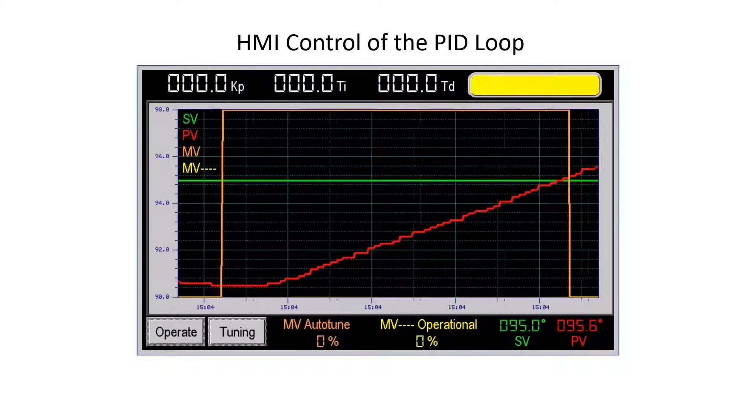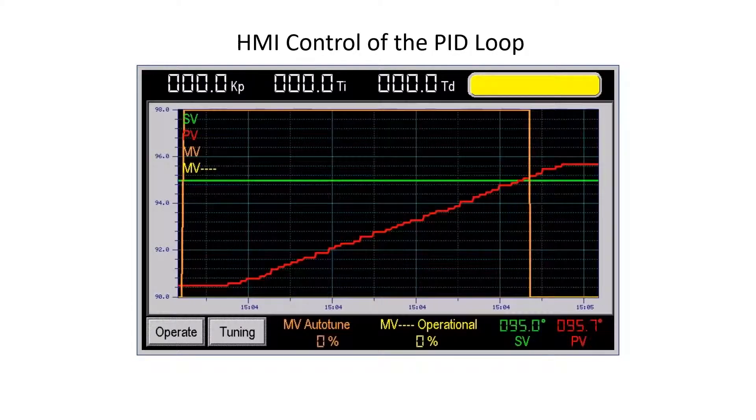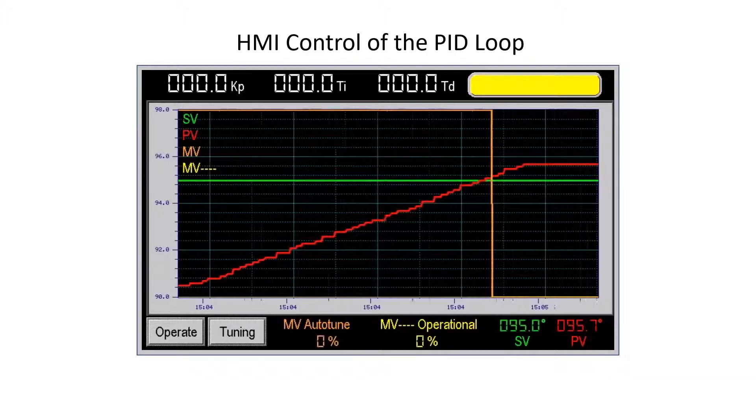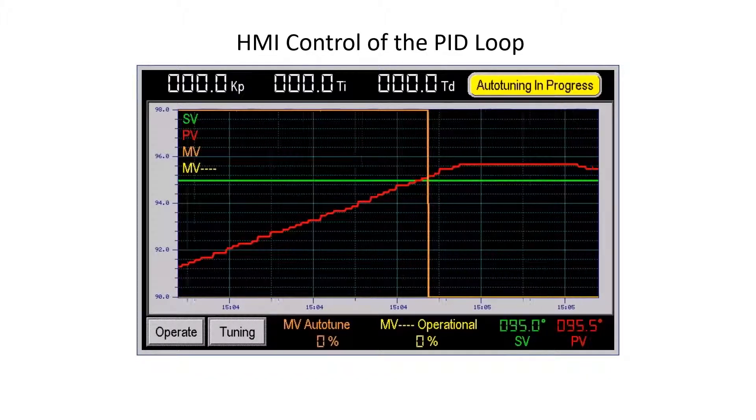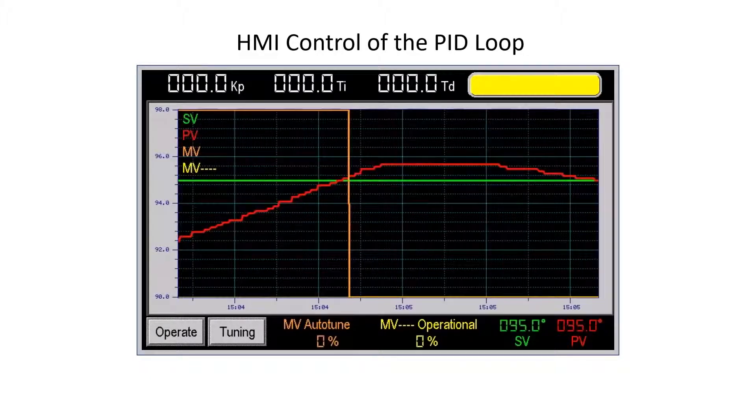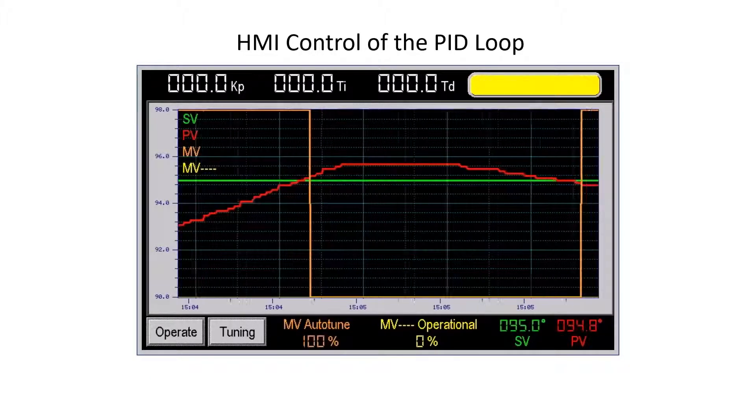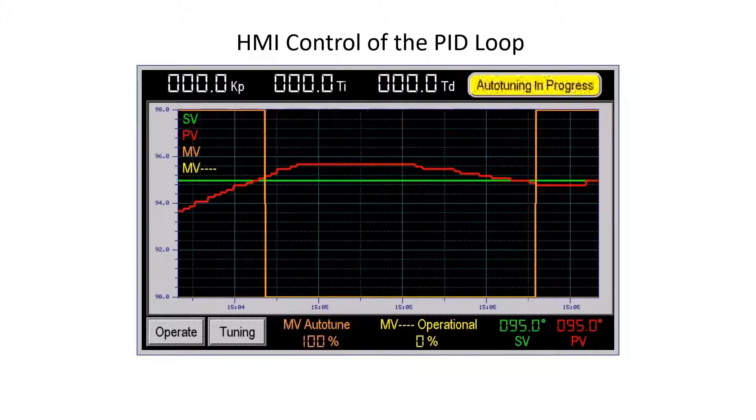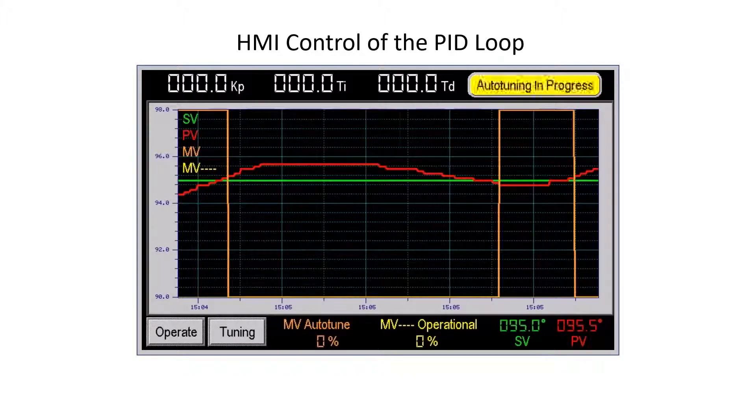The auto-tune uses the Ziegler-Nichols closed loop auto-tuning method. The auto-tune MV will go to 100%. The PV will increase and cross the SV and the MV will go to zero. This will occur three times.